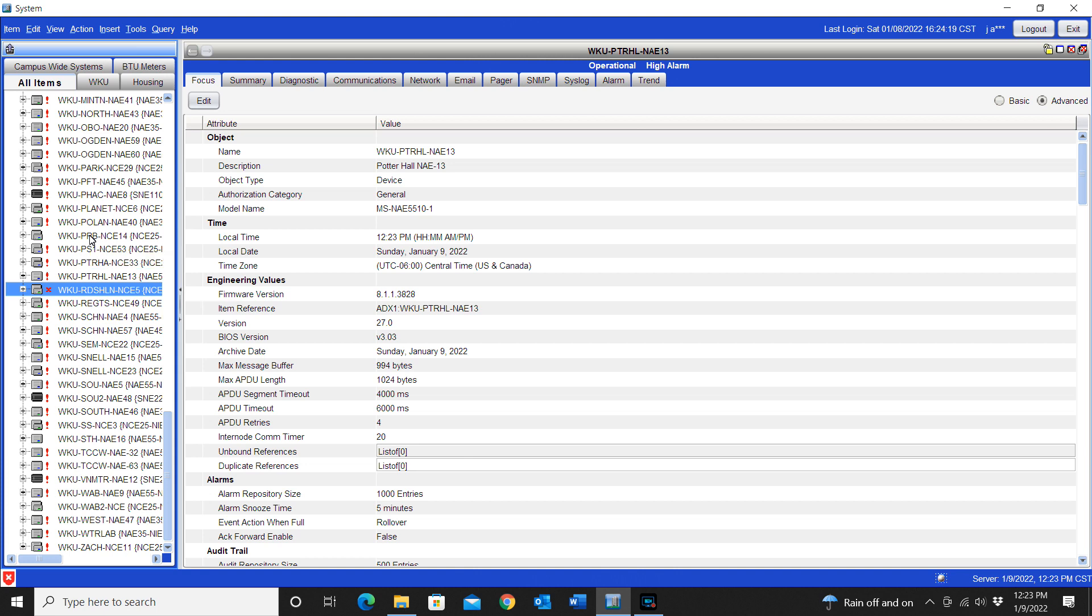If there are any strange characters or anything like that, if you have done a recent update to your system, an upgrade to your system, any kind of strange characters can cause that issue. And that's how we learned of it ourselves when we first went to Metasys 11.